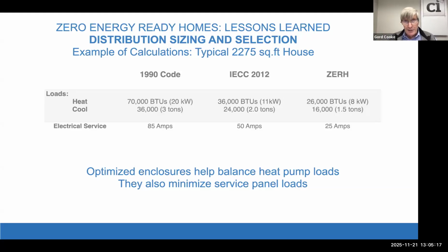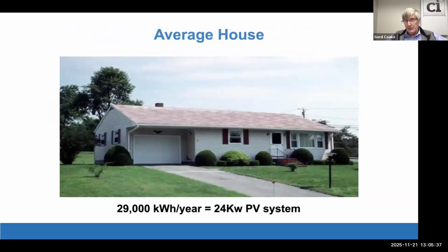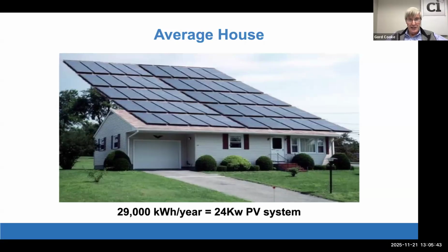So if you already have an air conditioner in a house, already planned for it, the heat pump in a low load house, a high performance house, doesn't really add anything to the grid sizing. But that's really what we're trying to do, is optimize those enclosures to help balance the heat pump loads and minimize service panel loads as well. So a little example is just showing, if you didn't upgrade the house, how many solar panels would you need? We want to be away from that.